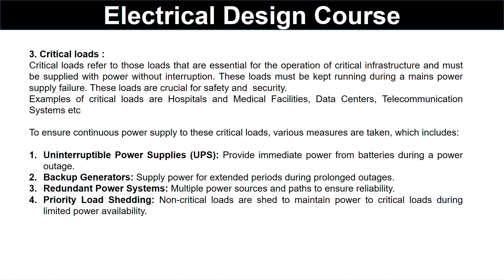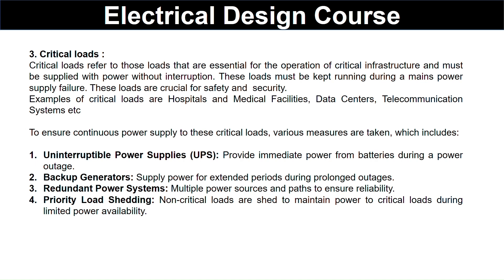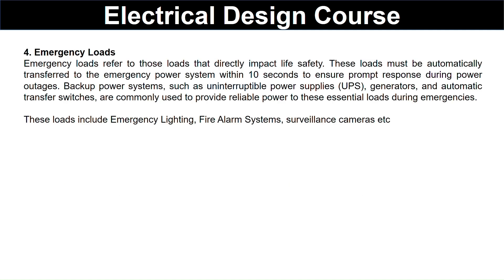Measures for critical loads include: uninterrupted power supplies, which provide immediate power from battery during a power outage; backup generators, which supply power for extended periods during prolonged outages; redundant power systems with multiple power sources and paths to ensure reliability; and prioritized load shedding, where non-critical loads are shed to maintain power to the critical loads during limited power availability.